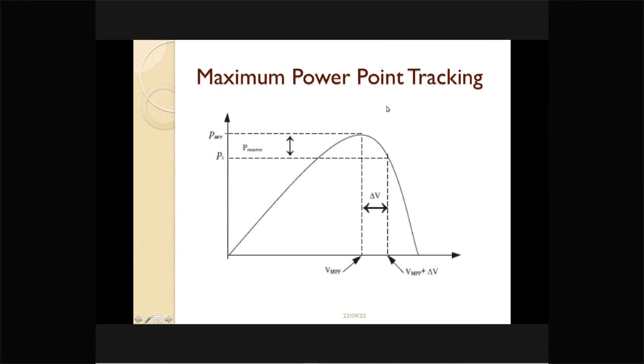However, under many circumstances, we may require to control the power output from a photovoltaic system, just like in our synchronous machine, where we can operate at any point. Like that, we want to operate this. So we cannot go beyond the MPPT point, but we can always reduce the power output. This operation is called derated mode of operation, or dispatchable mode of operation, or power output based operation. So many names exist, where basically the photovoltaic system will be operated through a power command, not by the MPPT. However, the power command will have an upper saturation point, which is nothing but the MPPT point.